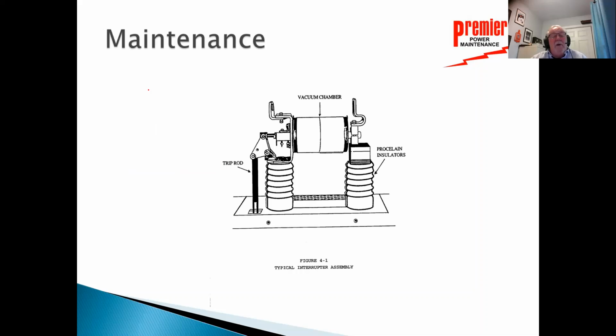Vacuum chamber, vacuum circuit breakers. I can't see the contacts in there. The best thing I can do is contact resistance and do a high voltage vacuum test on that bottle.